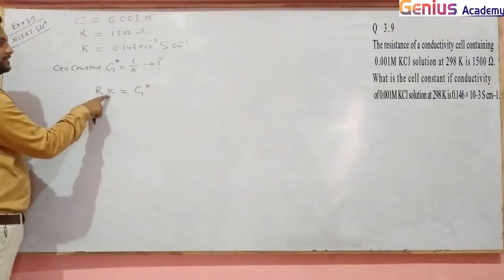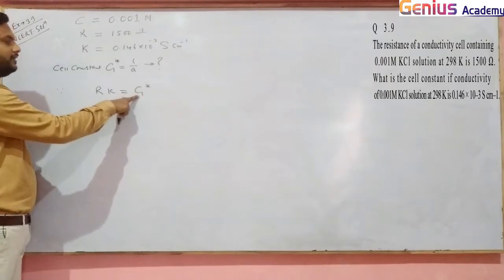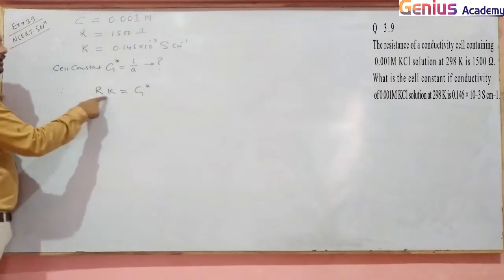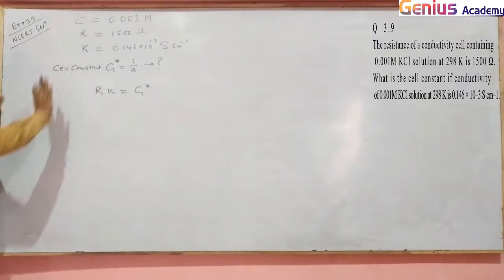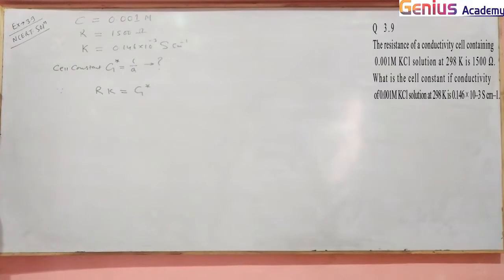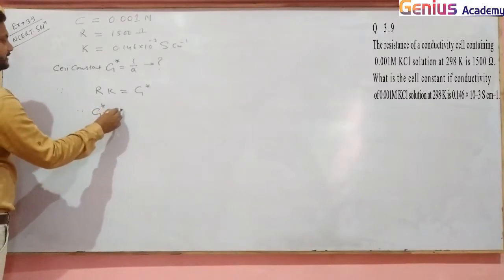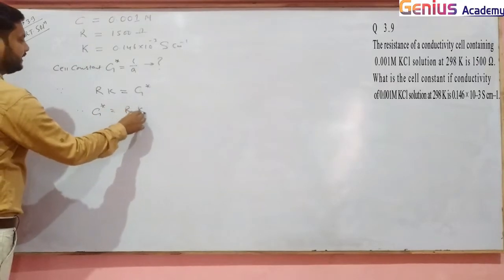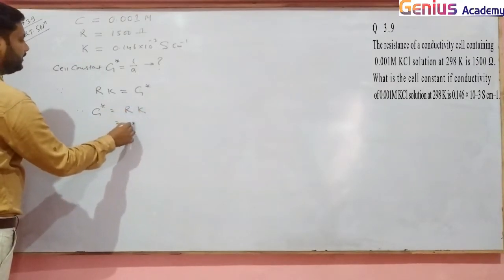R is resistance, K is conductivity, and G* is cell constant. If I multiply R and K, I get the cell constant directly - no need for concentration. Therefore, cell constant equals R × K. R value is 1500 ohm.